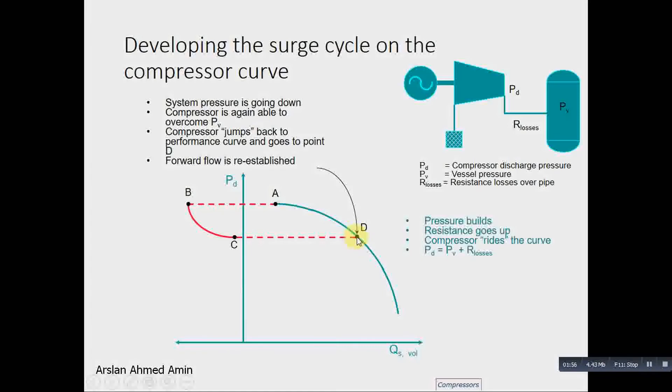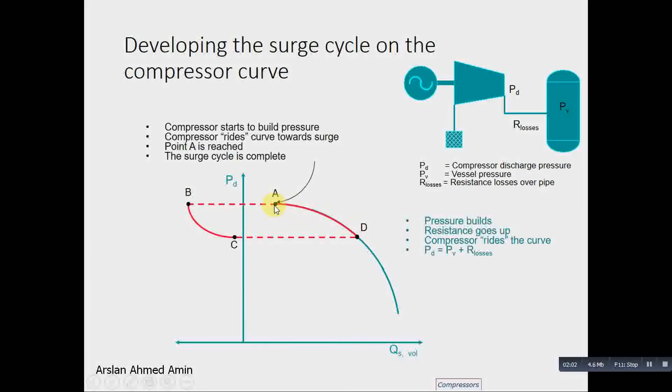At point D, when it reaches point D, it again goes to point A. So this is a typical surge cycle, which is faced by the compressor. This is mainly due to the buildup of high pressure at the header side. Compressor flow starts oscillating between these values.